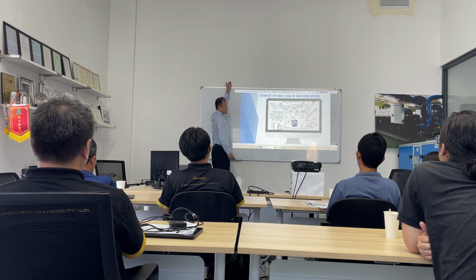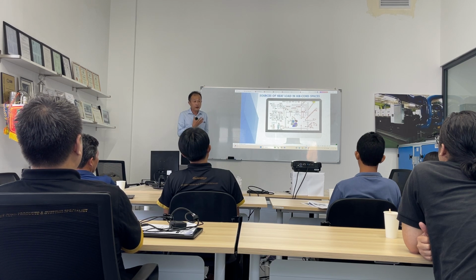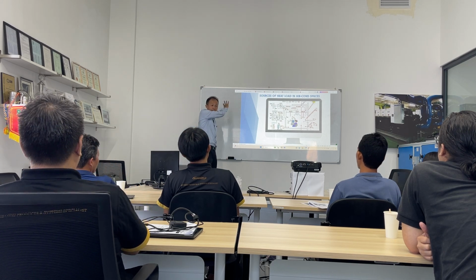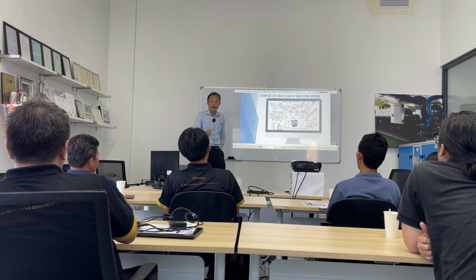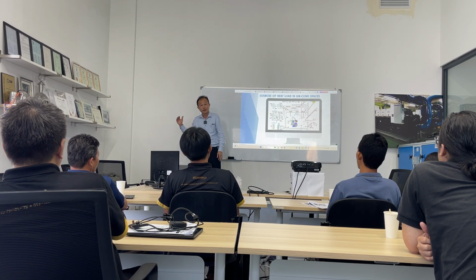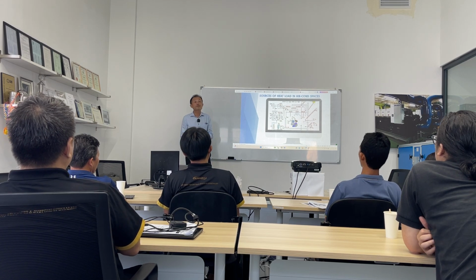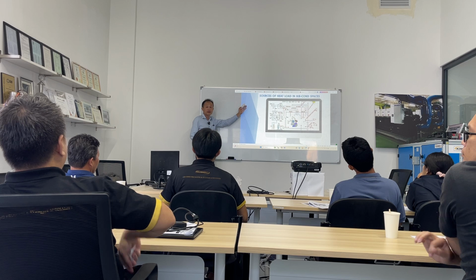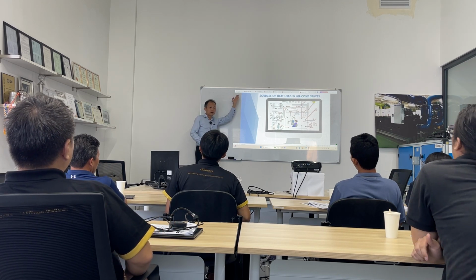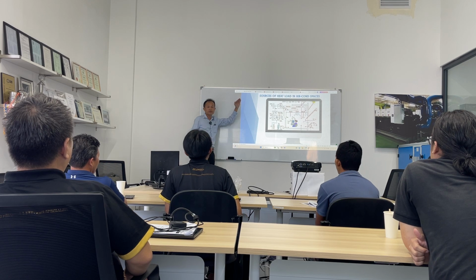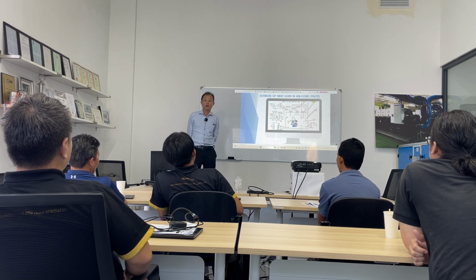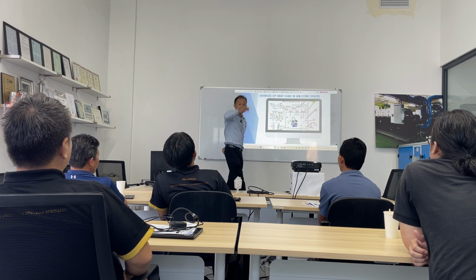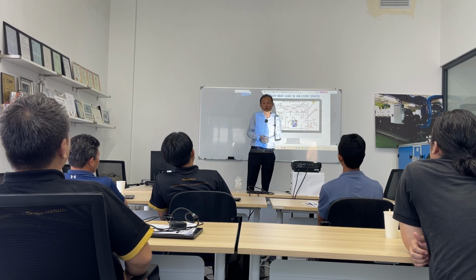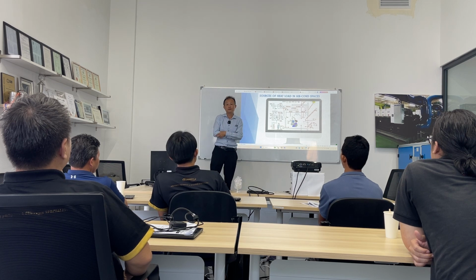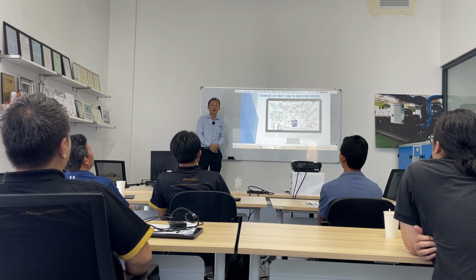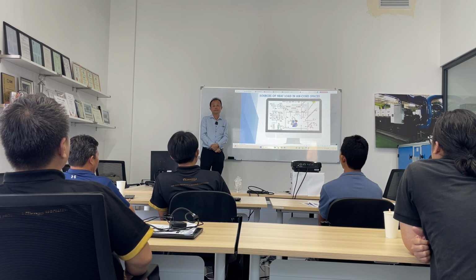So, and then next door is the warehouse, right? It's not an aircon space. The temperature next door is higher than the aircon space here. So when there is a temperature difference, there will be heat transfer. So they call it partition heat. This is a partition where the temperature next door transfers heat due to the temperature difference. Okay. Now the upstairs level 1 is not operating aircon, so it's higher temperature. The heat also will transfer from upstairs through the ceiling. So that's another source of heat. Understand?